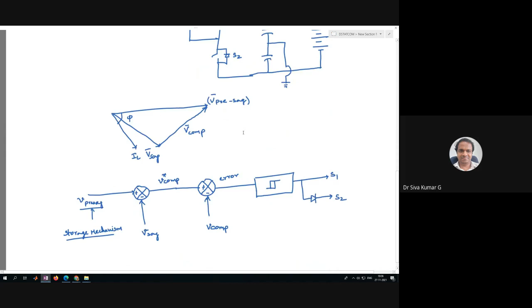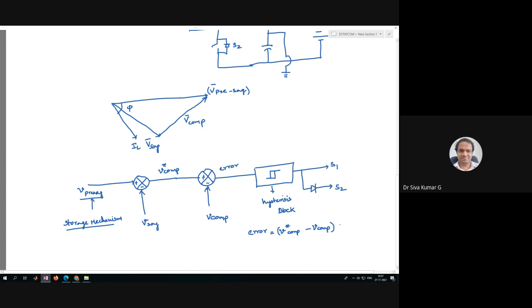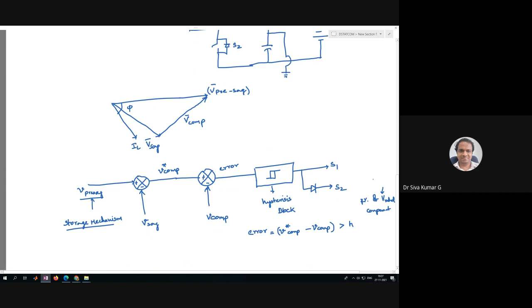This particular hysteresis block, we can very well use for this voltage control also. The hysteresis block basically works based on the error. The error equation is V star of compensator voltage minus V compensator is greater than the value, maybe the H band. Maybe you can consider the voltage of 2% or even 1% of the rated compensator voltage. What is the rated compensator voltage? It is 50% of the rated supply voltage.